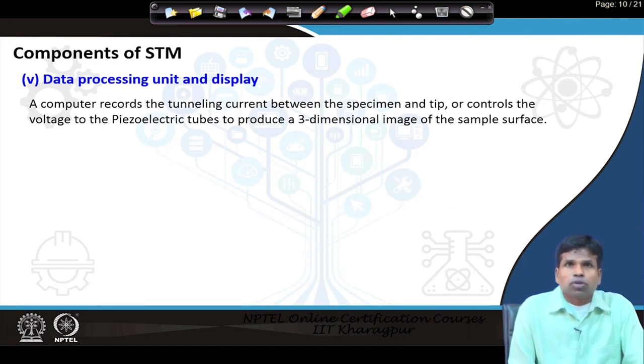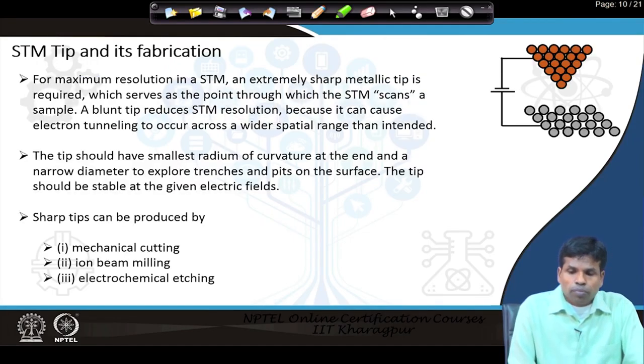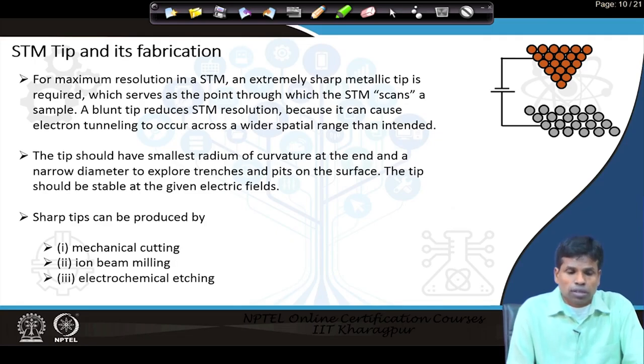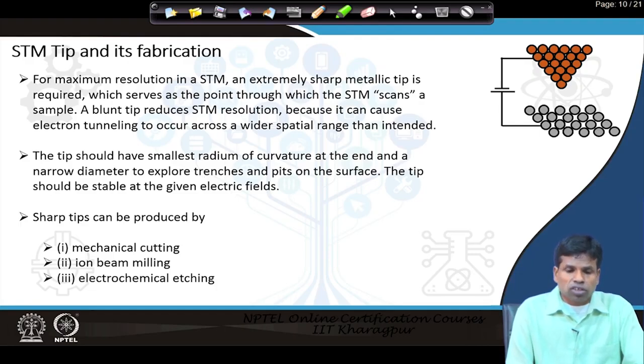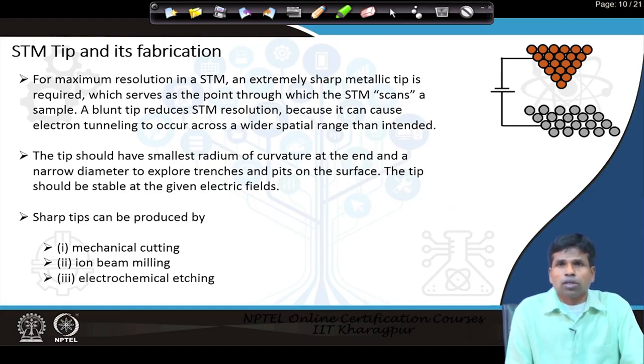Then we have the data processing or display unit. A computer records the tunneling current between the specimen and tip, and controls the voltage to the piezoelectric tube to produce a 3D image of the specimen surface. Normally, for scanning tunneling microscopy, the operator prepares the tip themselves. It is not commercially purchased — a fresh tip has to be fabricated to get information at the atomic level.